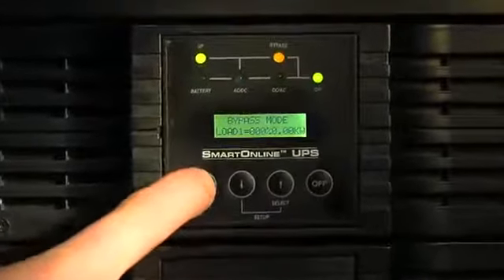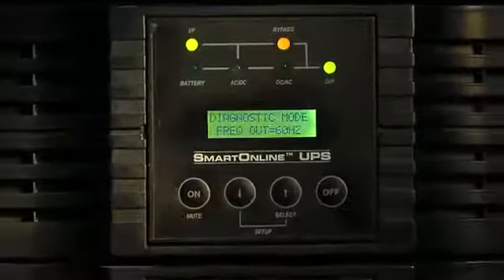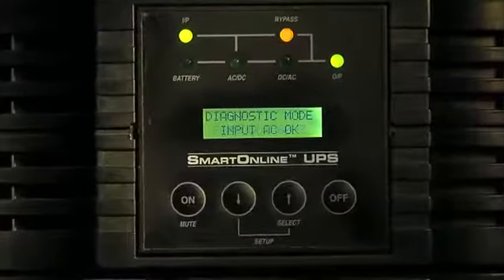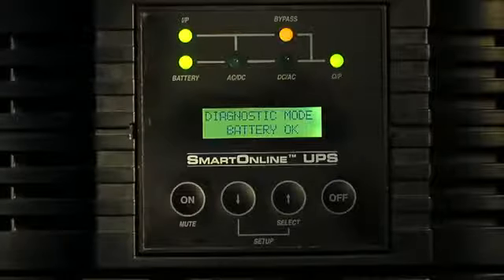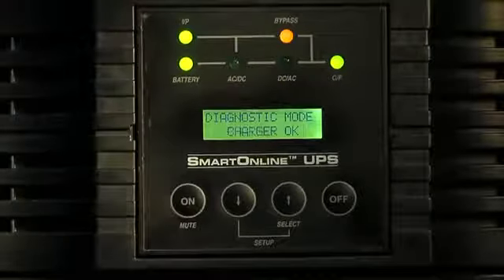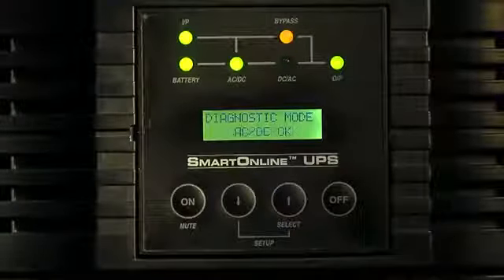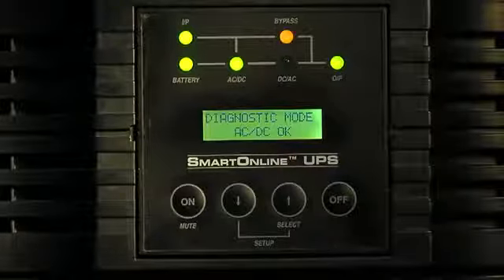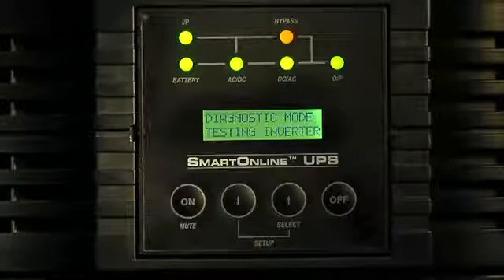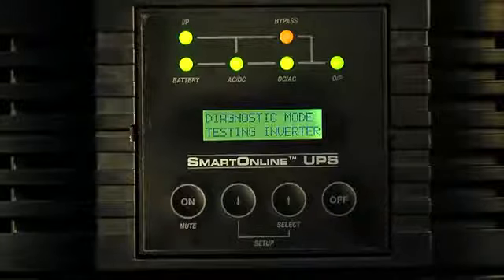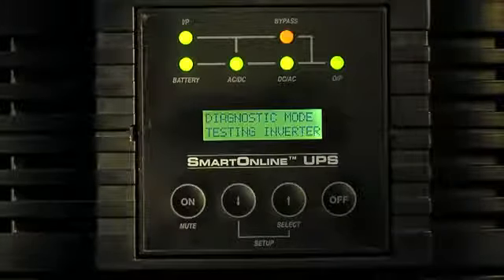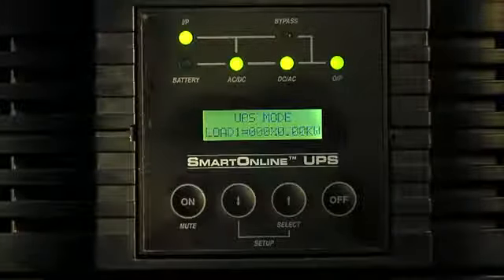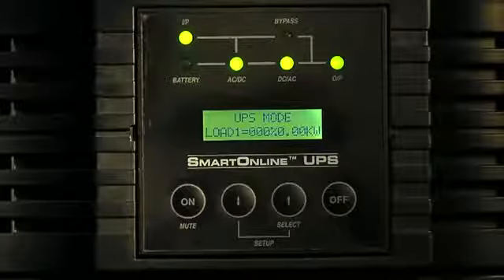Having replaced the power module, we're now ready to power up the replacement module. By pressing the on button, we initiate a diagnostic process. It tests the rectifier, the inverter, and various internal functions. There the rectifier has begun. Soon the inverter will restart and the load will be back into a double conversion served state. There we go. We're ready for the next step in the swap process.